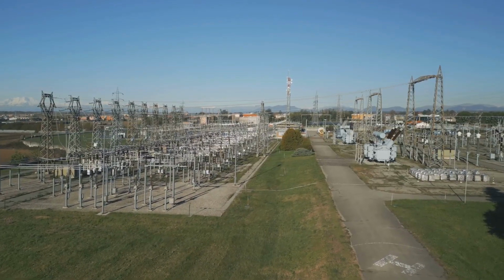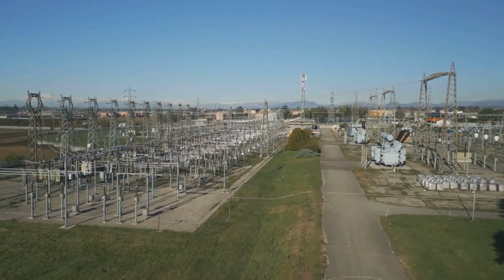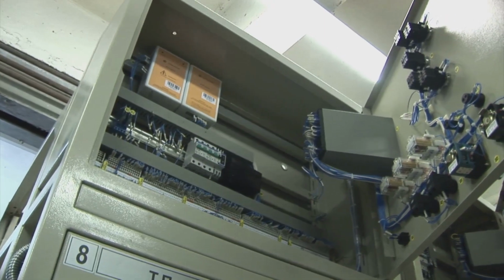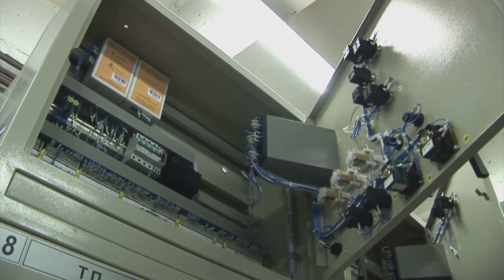During a fault event, especially for inverter-based DERs, there's a risk of unintended control behavior or rectifier response introducing DC components.